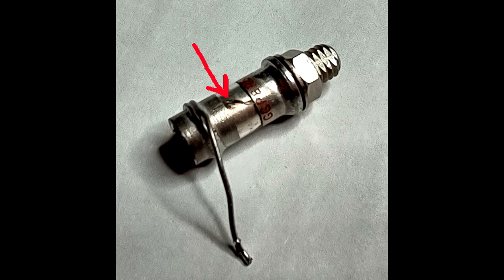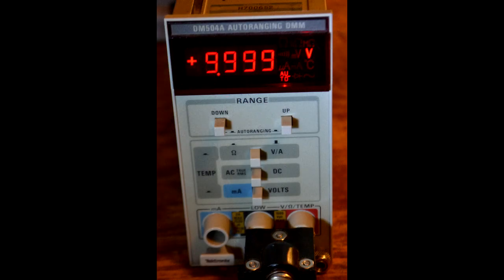Replacing these caps, or finding a replacement, could be difficult, because most of the stock of small trimmer caps at the museum are the type used in plug-ins, which do not have a high voltage rating. Leaving the trimmer out greatly reduces the AC accuracy even at 1 kHz, let alone the 10 kHz limit in the instrument specifications. If I had replaced any of the other components, I would have had to do a complete recalibration, which, as I explained before, is impossible given the lack of calibration sources.